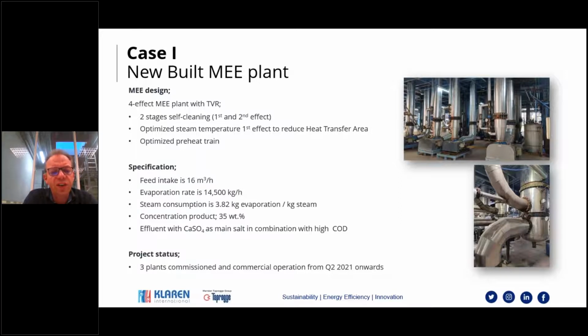Looking at the composition of this effluent, we're talking about an effluent with gypsum as the main salt, also giving the fouling issue, in combination with a very high COD. And this COD with temperature will also give coking as one of the contributing fouling mechanisms.